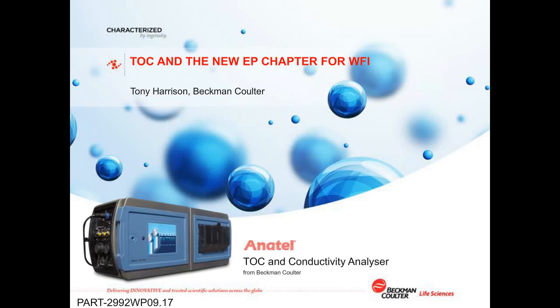Sure. Well, the UV light is critical to the analysis. And in fact, in most TOC analyzers, the UV light output is not monitored directly. So when a UV lamp starts to age and its output starts to drop off, then the TOC analyzer will no longer be oxidizing correctly, and the analyzer will underreport. And for this reason, the PAT 700 directly monitors the UV lamp output and automatically switches to a standby UV lamp should the main lamp begin to fail.